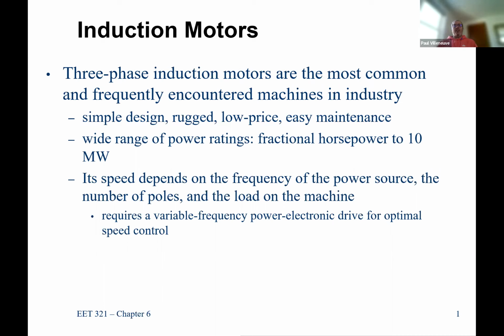For the most part, if you keep the area clean around them, so you're not exposing them to water or chemicals that could degrade the insulation, as long as the bearings are well maintained and your shafts are aligned. One of the things that really destroys motors is when you couple a motor to a load that is not perfectly aligned, and can move up or down in position. Over time that causes some bearing scoring, and you can get damaged bearings that way. You can also damage the shaft. But if you do a relatively good job of aligning it, it should last for years, and the maintenance is almost negligible. If the bearings fail, you can sometimes replace them.